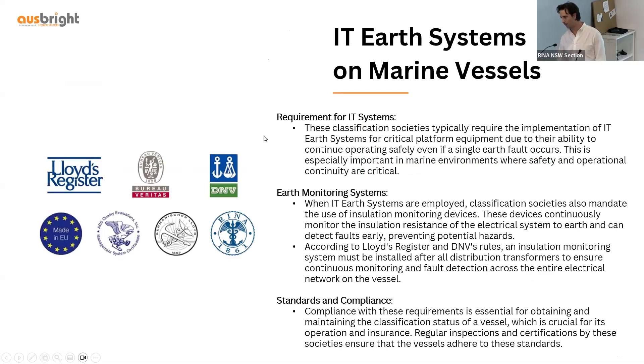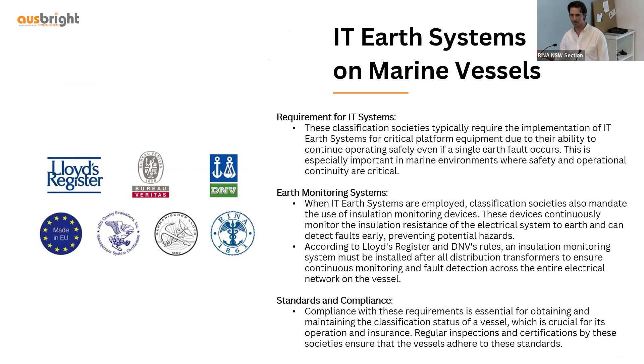Moving on to marine examples — as we can see, IT Earth systems prioritise plant operation, and that's why marine regulations require IT Earth systems on vessels. You can have an Earth fault and your steering motor is not going to stop — it's going to continue to run. Whether you're in harbour or another event occurs, you want your plant to continue operating while there is an Earth fault. They will also instruct you to use an Earth monitoring system, as there are negatives to the IT Earth system.